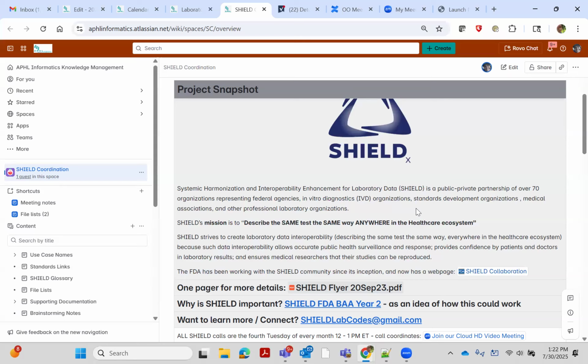And so from that meeting, the IVD vendors formed an organization called the IVD Industry Connectivity Consortium, or IICC, and they went off and created an IHE profile that describes the HL7 messaging that people should be using from an instrument to the LIS. That's the IHE LAW work, and that's been published for a while now, and it's become the CLSI AUTO16 standard, which is going to get updated later this year. And that was the first thing. So now the instruments can carry the LOINC code when they provide the result back to the LIS.